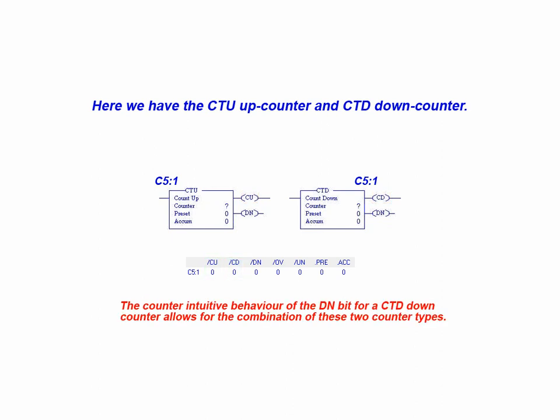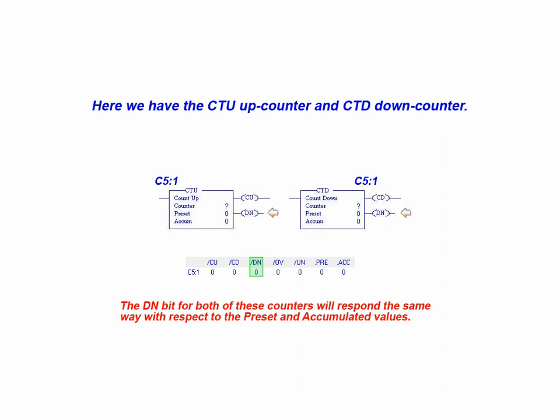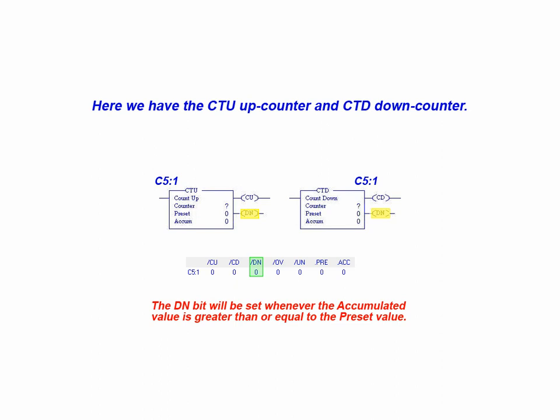The counterintuitive behavior of the done bit for the CTD down counter allows for the combination of these two counter types. The done bit for both of these counters will respond in the same way with respect to the preset and accumulated values. The done bit for each counter will be set whenever the accumulated value is greater than or equal to the preset value.